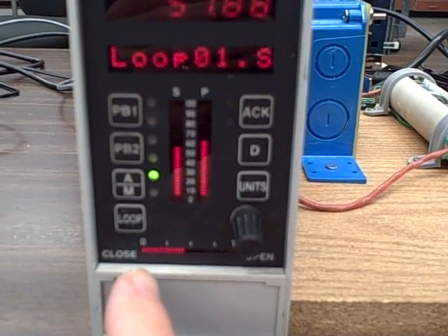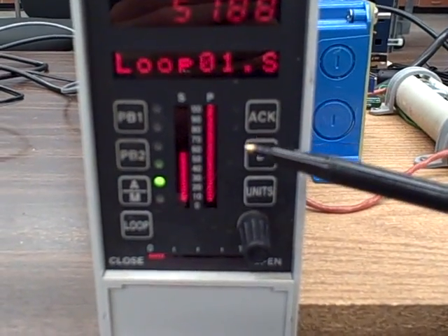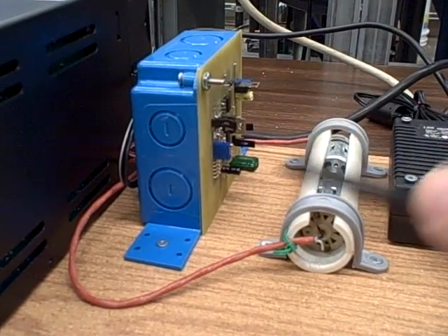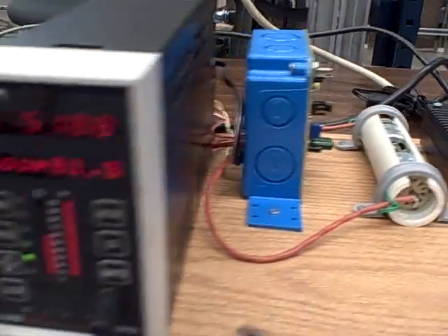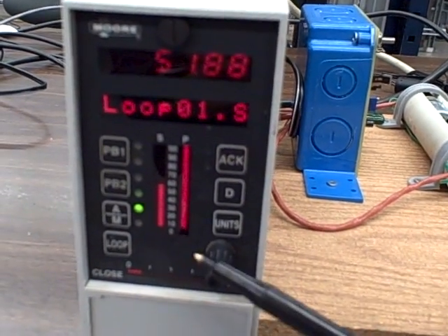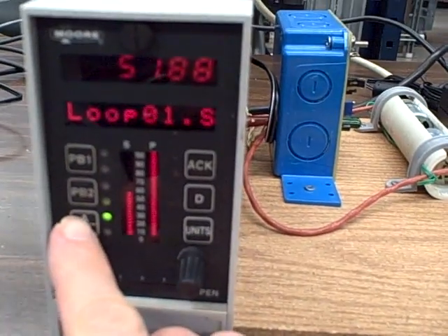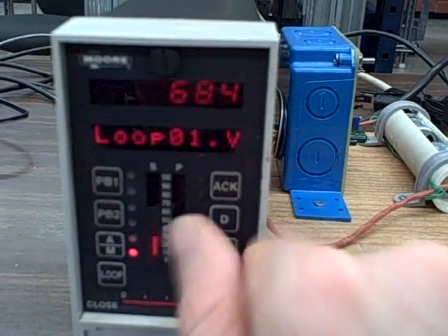There we go. Something made the motor go a little bit faster. Now the controller once again is taking inappropriate action. It's driving the output signal down, which in this case, because we've reversed the variable speed motor drive action, makes more power go to the motor, makes the motor spin faster. Once again, an example of positive feedback that results in complete instability. Let's switch back to manual mode. I'll basically drive the motor off.